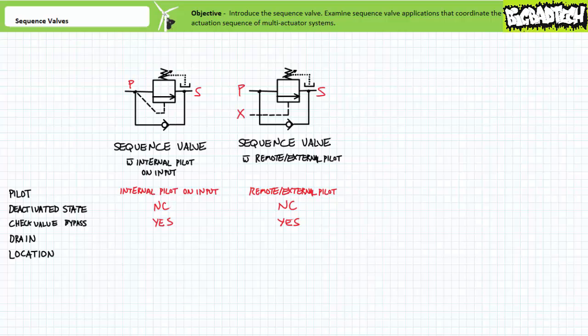Customarily, the primary or input port on a sequence valve is labeled P for pressure, and the output or secondary port is labeled S for sequence. If the sequence valve uses an external pilot port, let's call it port X. Sequence valves ordinarily include a check valve bypass because they're employed in regions with bidirectional flow paths. The check valve bypass allows the sequence valve to control pressure in one direction and be bypassed in another. If the sequence valve does not include a check valve bypass internal to the valve enclosure, a separate external check valve must be employed. Sequence valves require an external drain since their output port is pressurized. External drains are symbolized by a dotted connection to tank, and the drain port is customarily labeled D.